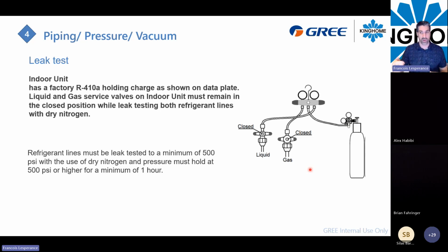Because if you just spray your soap all around the valve and wipe it away after 30 seconds, it will not work properly. You will have to leave the soap working and dry just a little bit, and maybe you will see some micro leaks after 15 minutes. So make sure your pressure test is good enough to avoid having to redo all your stuff because you have a leak or something.